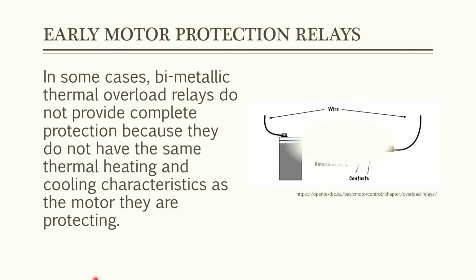In some cases, bimetallic thermal overload relays do not provide complete protection because they do not have the same thermal heating and cooling characteristics as the motor they are protecting. We all know we have a lot of motors being sold in our malls and the market. Those motors come from different manufacturers, and those manufacturers have the freedom to pick what kind of metal and what type of conductor they are going to choose to build their product. And for that, there is no universal type of metal to be used for the universality of the motor. And for that, the metal used in the bimetallic strip might not be the same as the metal or the conductor used in the motor. And for that, there is a discrepancy in the thermal heating and cooling characteristics of both metals.